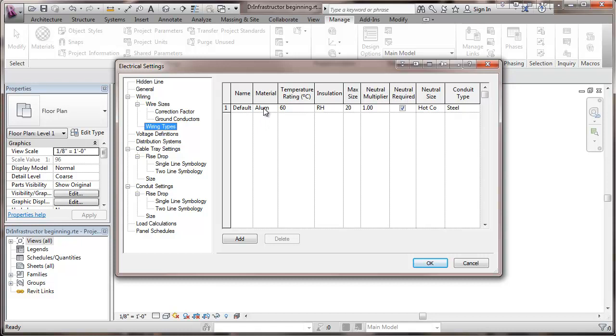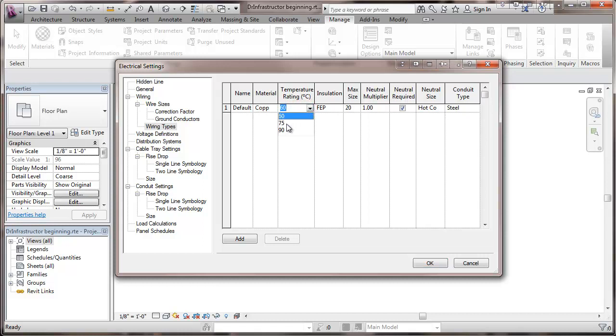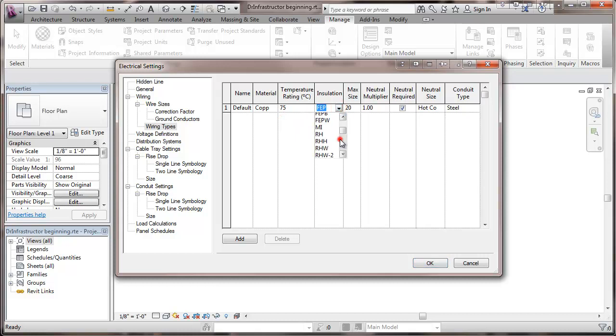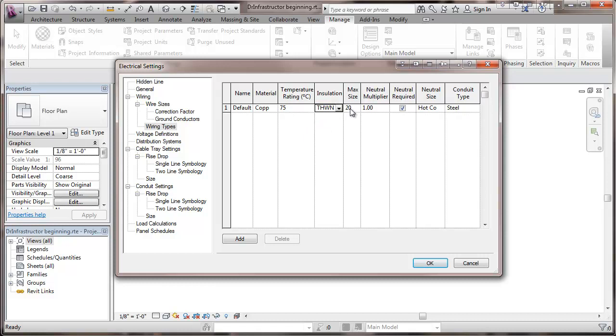So I'm going to go in here and I'm going to put my particular what I would normally be using. So I'm going to go to copper, 75 degree rated, THWN. And the maximum size table is a little deceptive. It says it looks like it's 20. But the reality is that's 2,000 MCM.